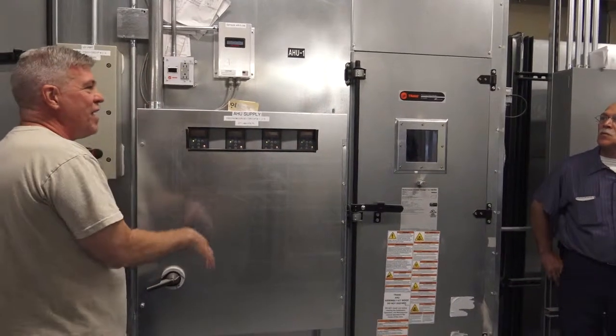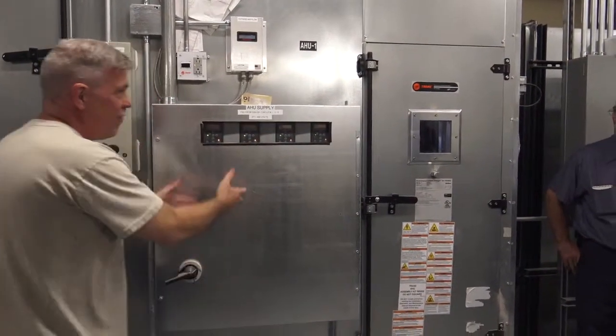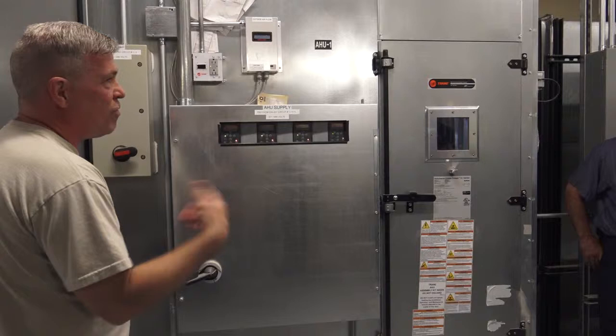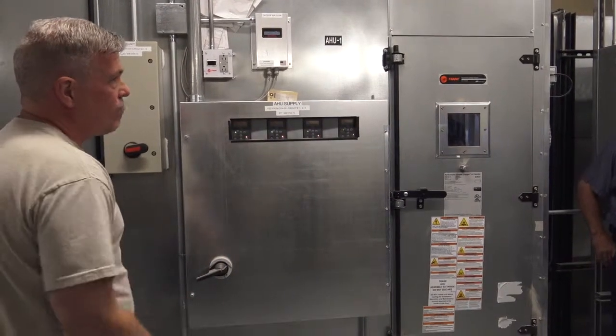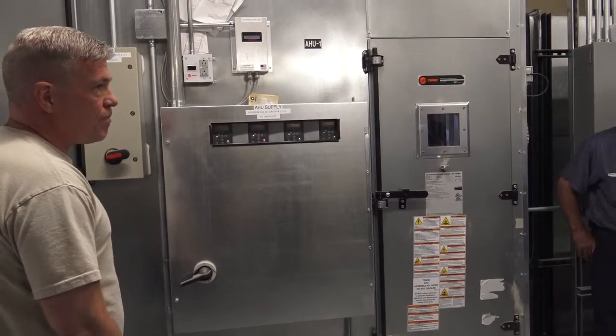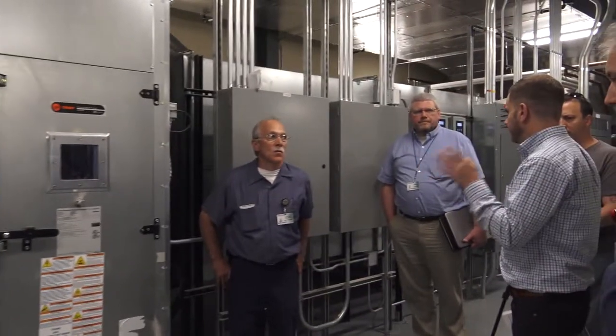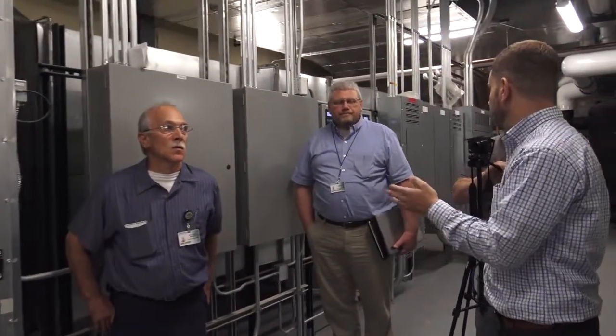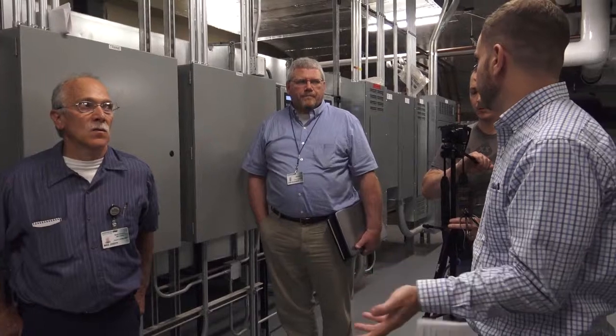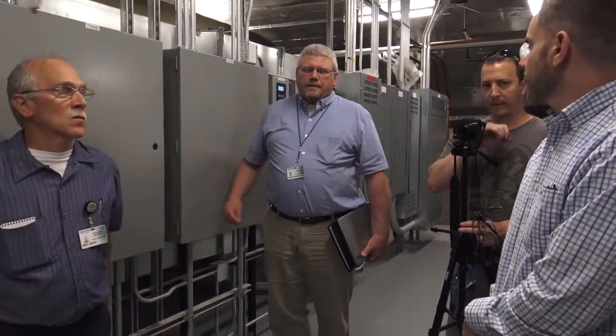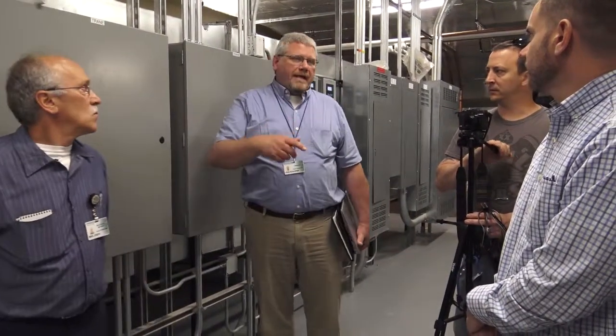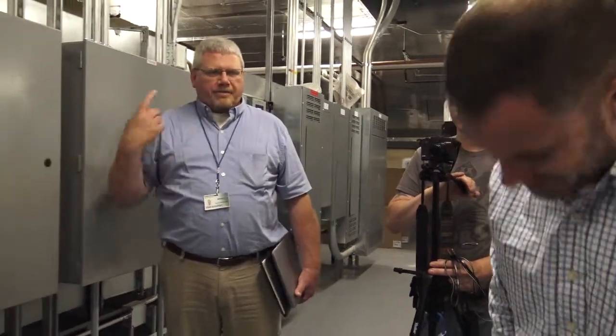That's why if you have a fan down, it's good to find out what's wrong with it, because it will just sit and spin backwards and create a problem. This building is only occupied 9 to 5, where the hospital is 24 hours, so you can wait a bit. The whole idea is if you lose a fan motor and it's going to take a week to get it, you can block that one off so air doesn't try to go the wrong way.